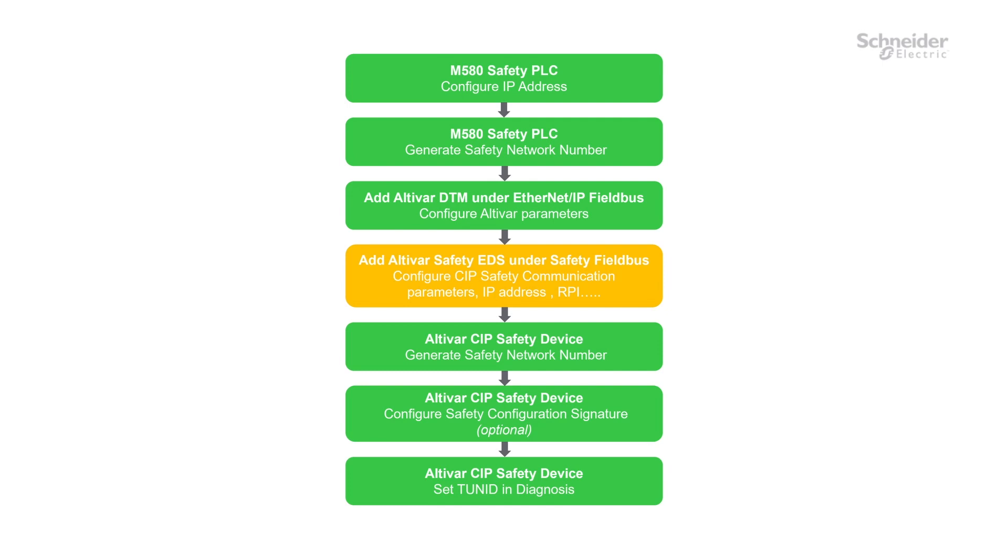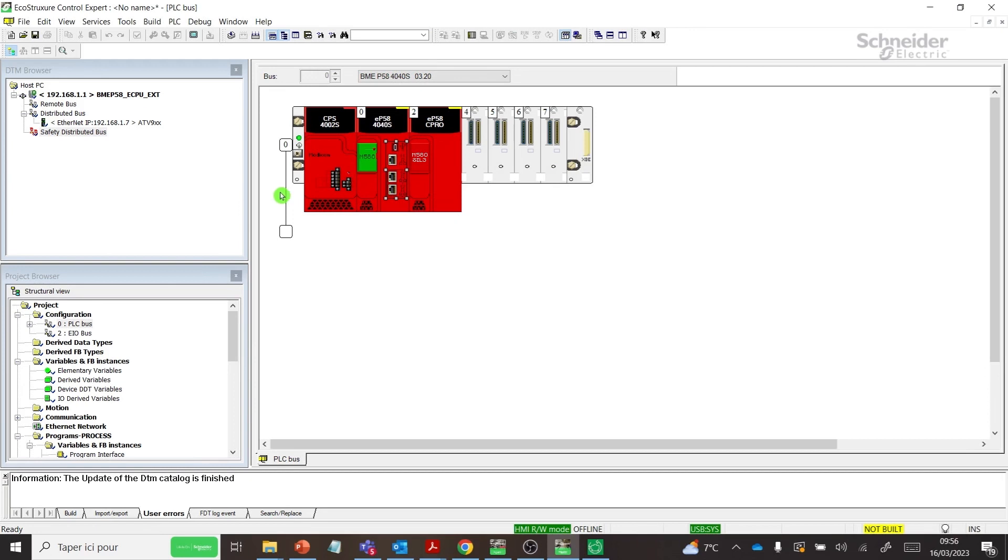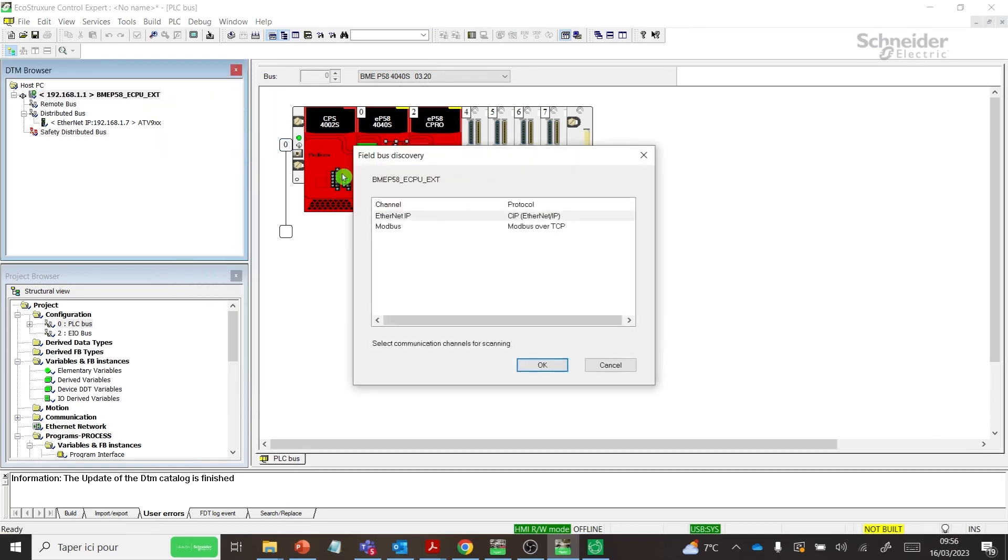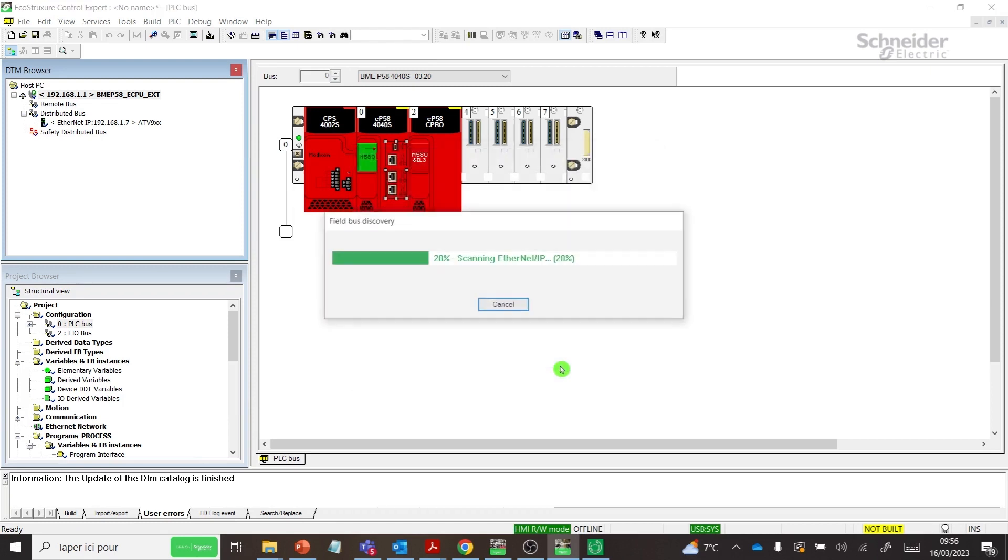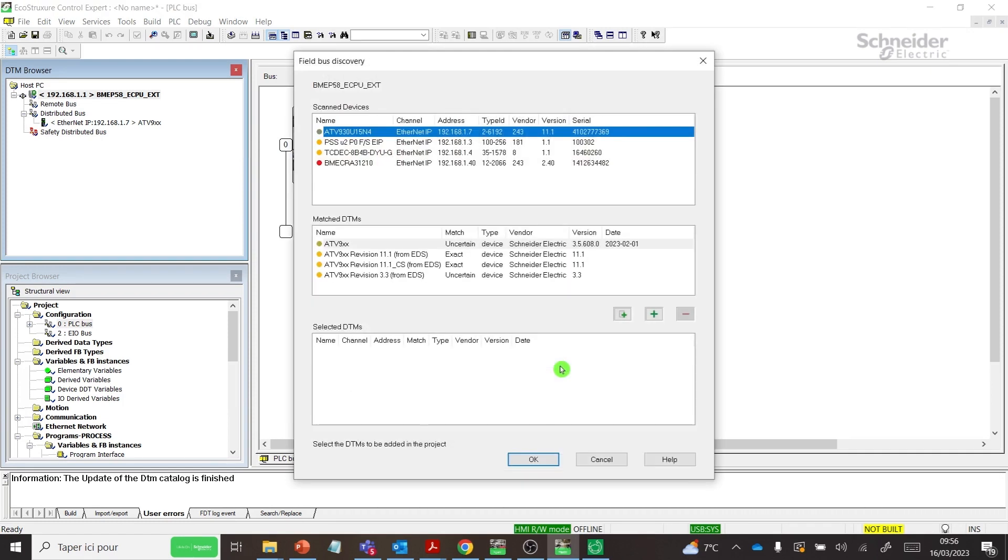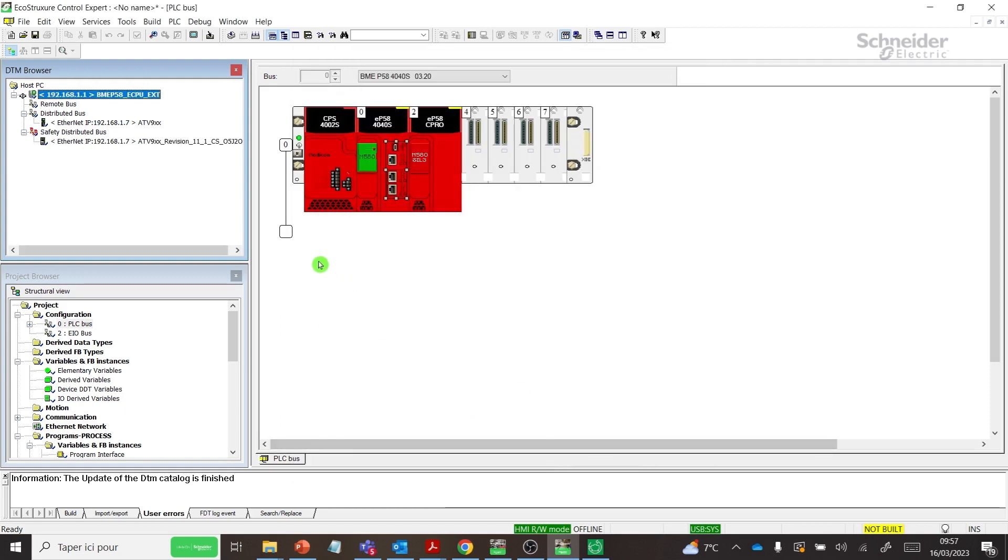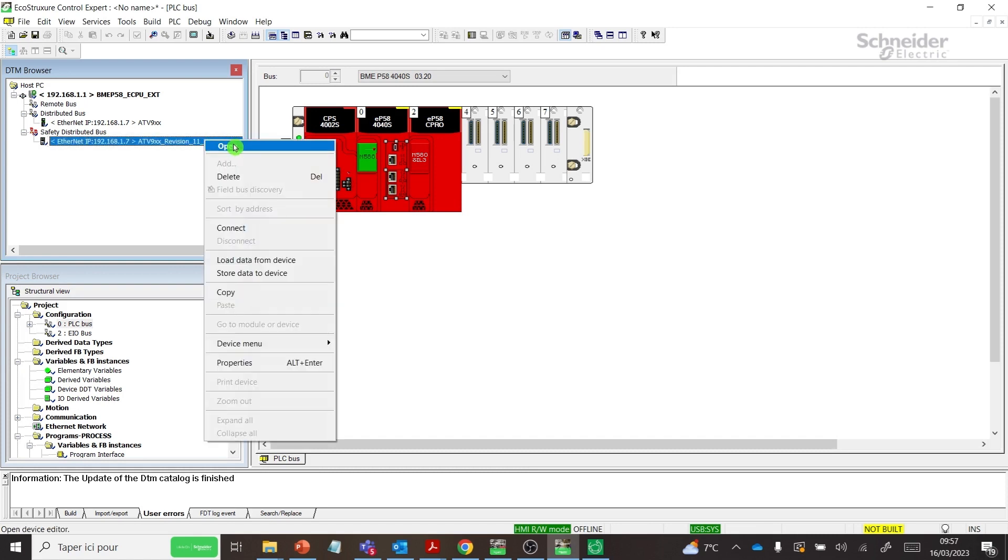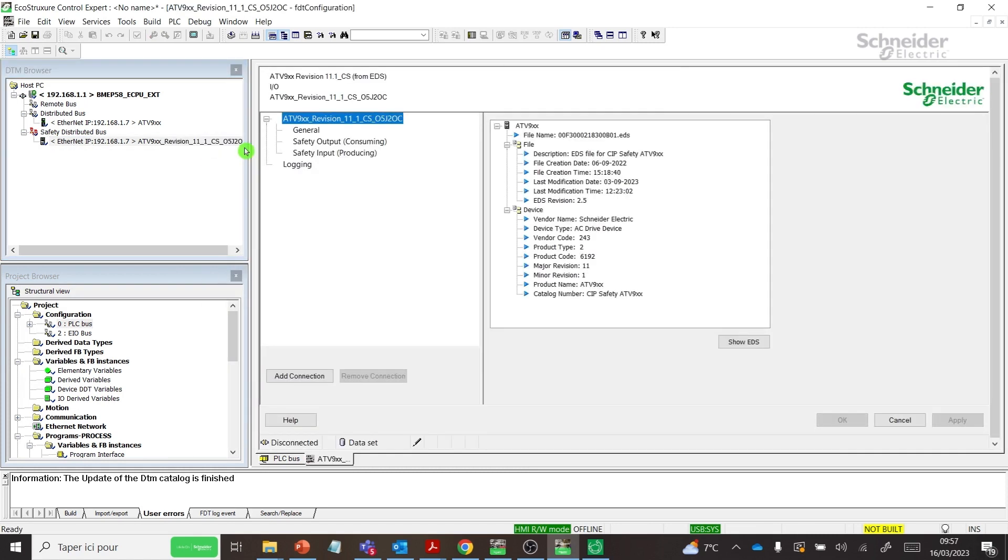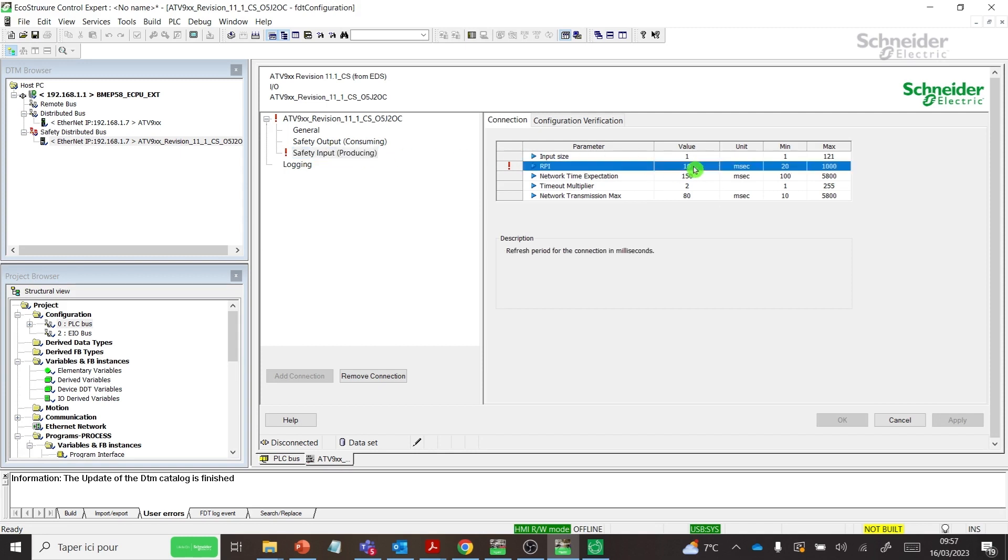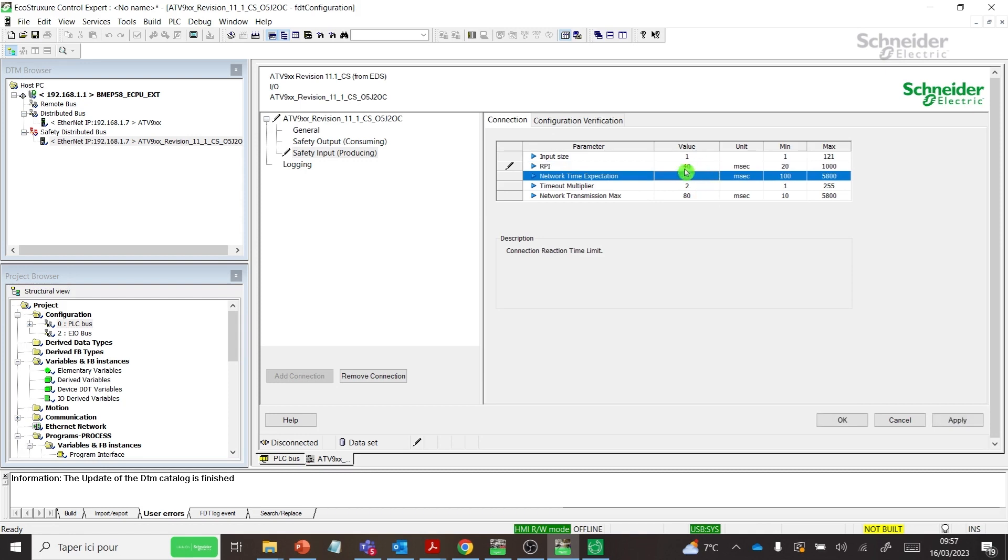Add Altivar Safety EDS under Safety Fieldbus. Right-click Master PLC DTM. Do a Fieldbus Discovery. Select the CIP Safety EDS files. Select Safety Input Producing. You must choose an RPI value between 20 and 1,000 milliseconds.